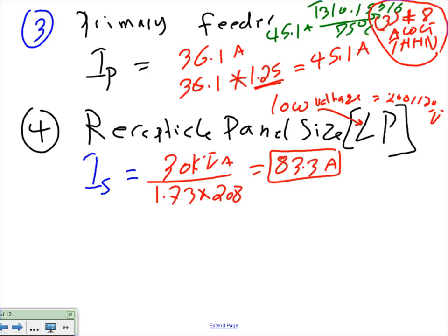Cool. Here's 83.3. Now if I'm to take full advantage of continuous load on this, full advantage, I would like to multiply it by 1.25. So take 1.25, multiply this by 83.3. I did not do this math, so I need somebody to do it.